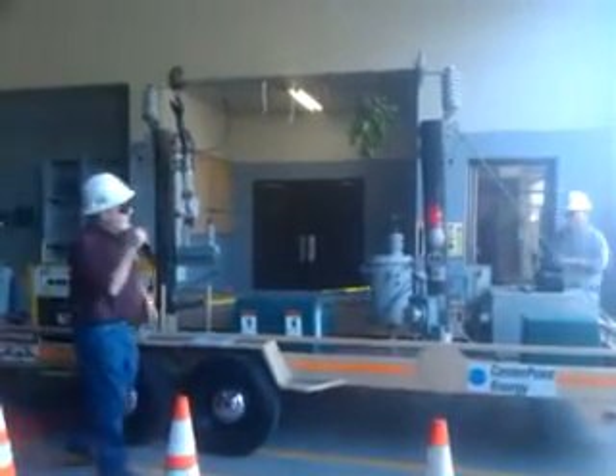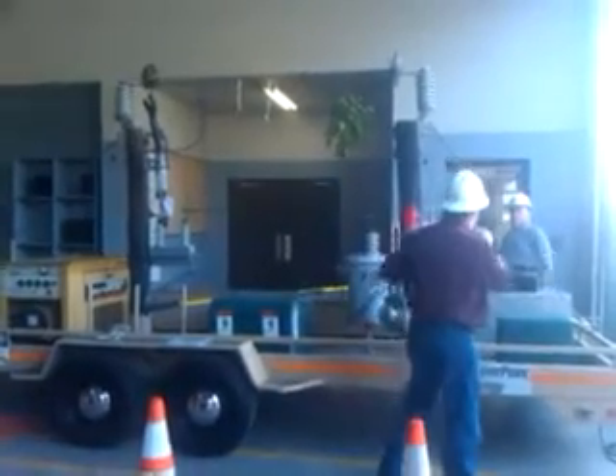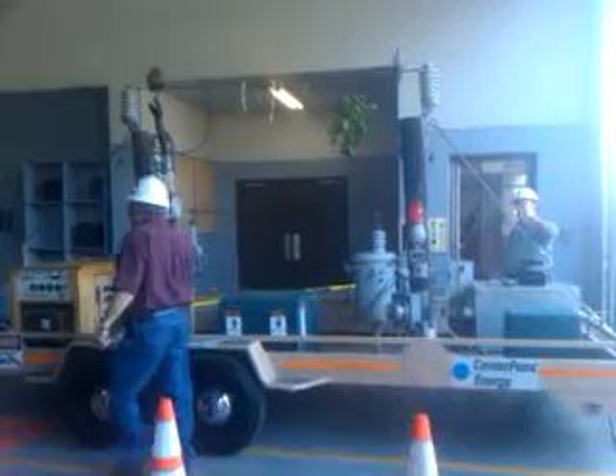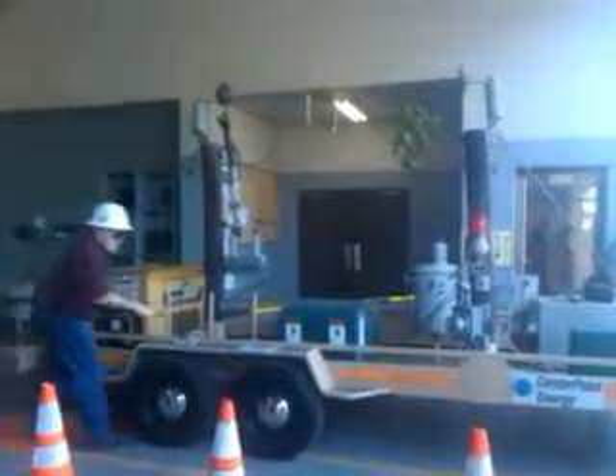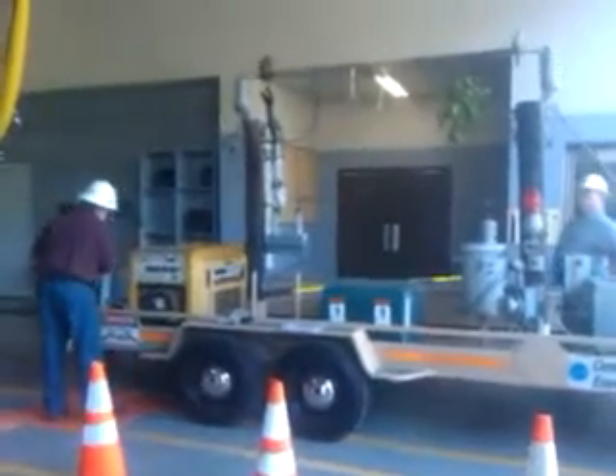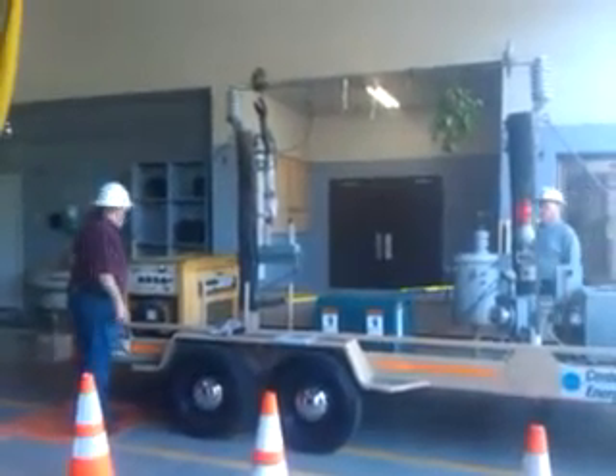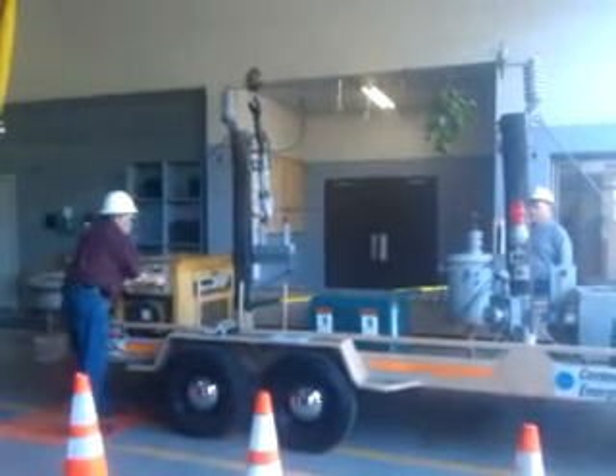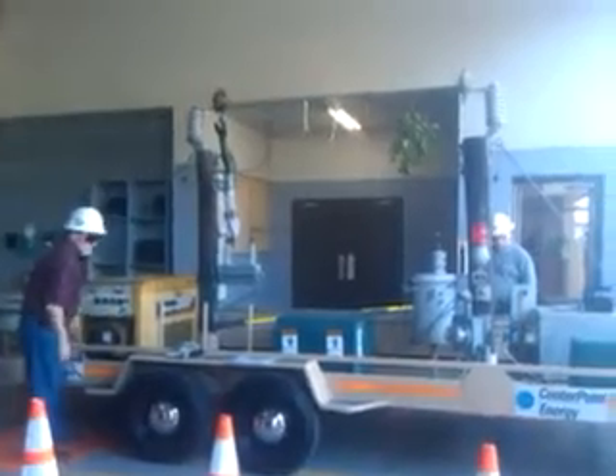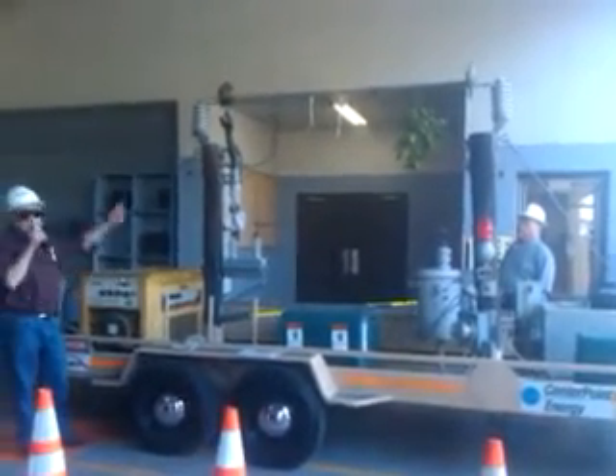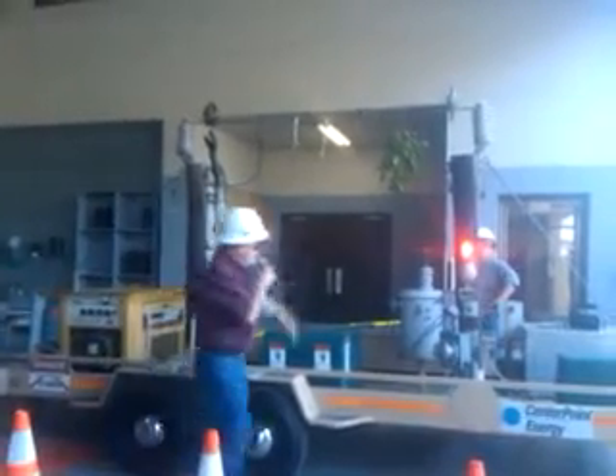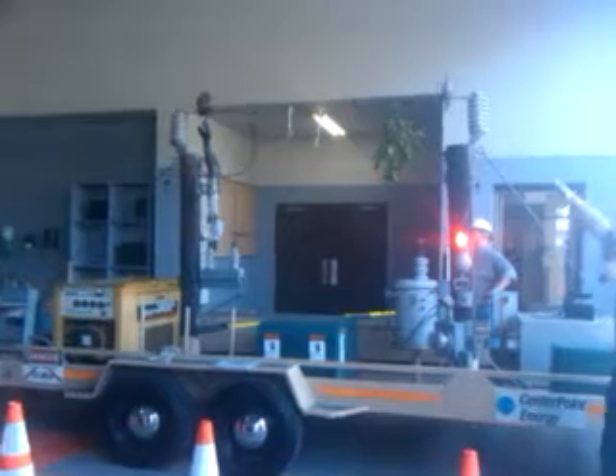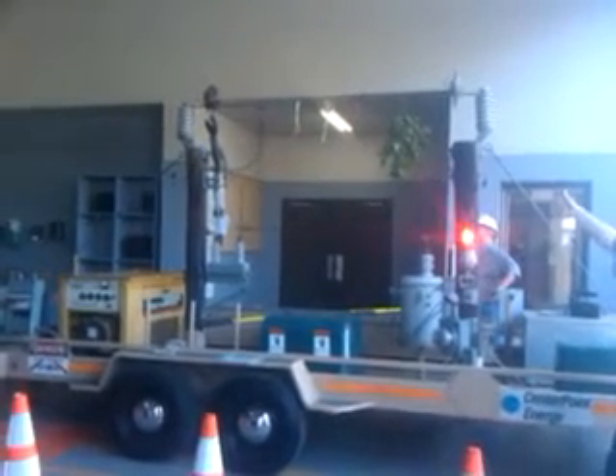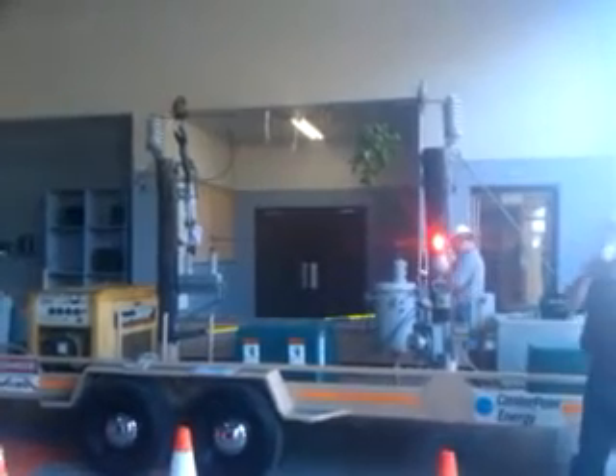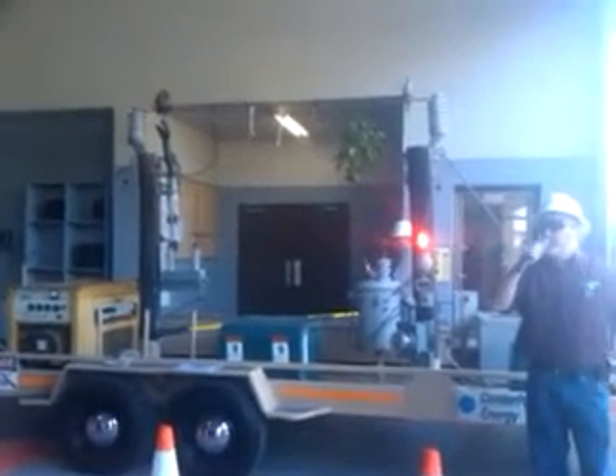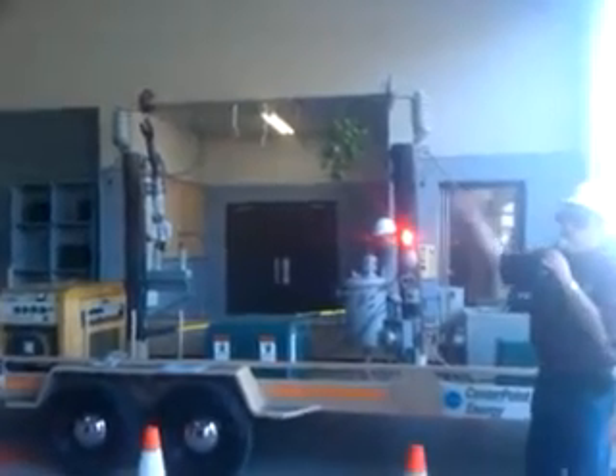Now, I understand Greg's going to do something here with what you call your hot stick. We're going to fire this up. Remember to turn your face, right? You operate breakers. Okay, watch the wire. It's hot. It's dead. It's hot. It's dead. It's hot again. Did the wire change? How many red lights do we have on our poles telling you that it's energized? We don't have any red lights. So always assume it's hot.